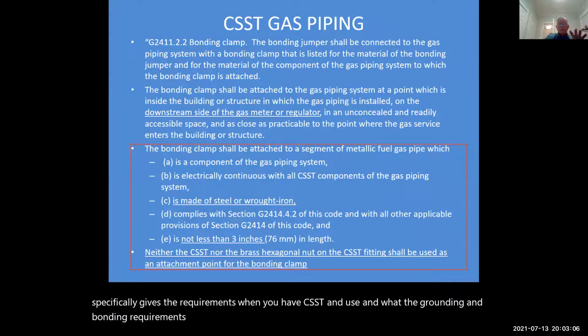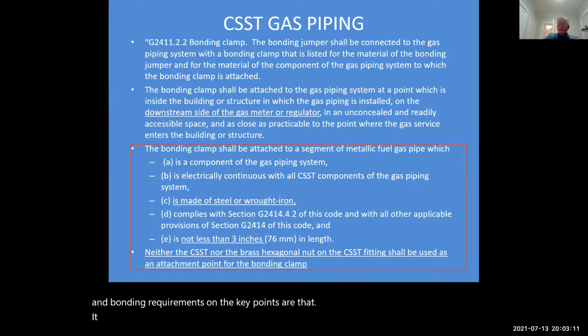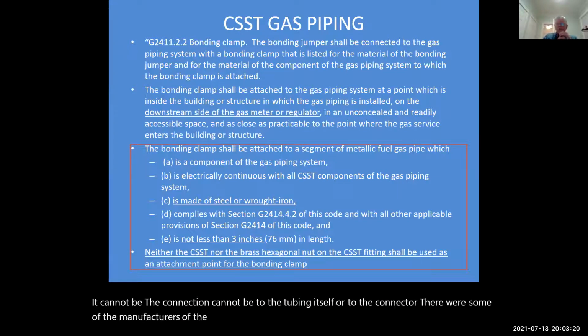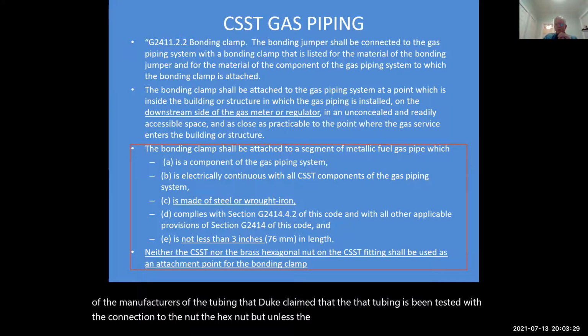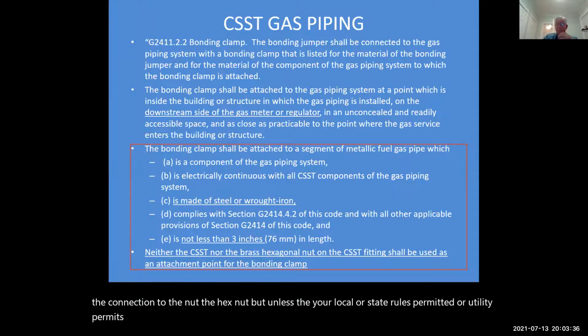And the key points are that the connection cannot be to the tubing itself or to the connector. Some of the manufacturers of the tubing do claim that the tubing has been tested with the connection to the hex nut, but unless your local or state rules permit it, or your utility permits it, it would not be technically legit to use it.